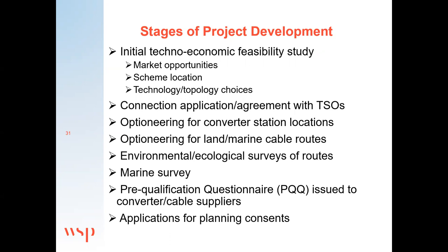And having chosen your ultimate cable route across the sea, you have to charter a ship and do a marine survey. At huge expense to the client. The marine survey will establish the geotechnical and geophysical details of the seabed. And as you can imagine, the seabed between the south of England and the north of France has got 2000 years of history on the bed of the sea. You may have archaeological sites, shipwrecks, you could have unexploded ordnance, you could have natural reefs, you could have many other telecommunication cables, power cables, gas pipelines, and so on. So a marine survey is an absolute prerequisite to understand where you can lay your cable in such a crowded area as the English Channel.